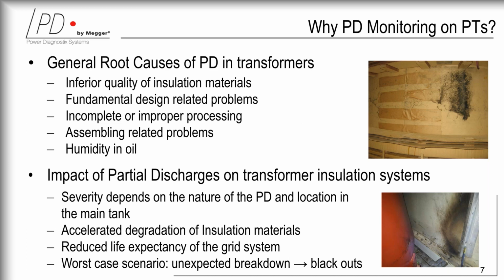And critical assets can be of two sorts, can be expensive assets. You know that a 200 MVA transformer can be 5-6 million euros at least. And at the same time, you can have a small transformer, maybe a 40 MVA transformer, that is placed in a key factory, or it's a step-up transformer of a nuclear power station, etc. So all this is a big issue.